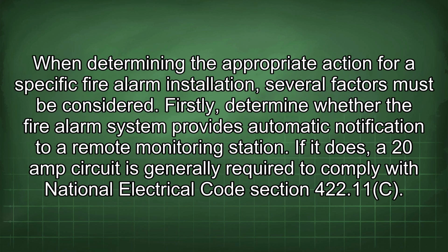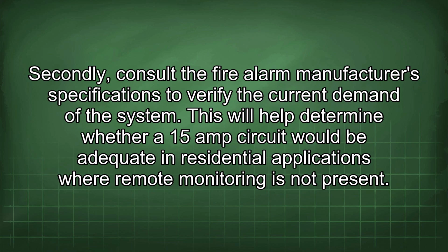When determining the appropriate action for a specific fire alarm installation, several factors must be considered. Firstly, determine whether the fire alarm system provides automatic notification to a remote monitoring station. If it does, a 20-amp circuit is generally required to comply with National Electrical Code Section 422.11c. Secondly, consult the fire alarm manufacturer's specifications to verify the current demand of the system. This will help determine whether a 15-amp circuit would be adequate in residential applications where remote monitoring is not present.